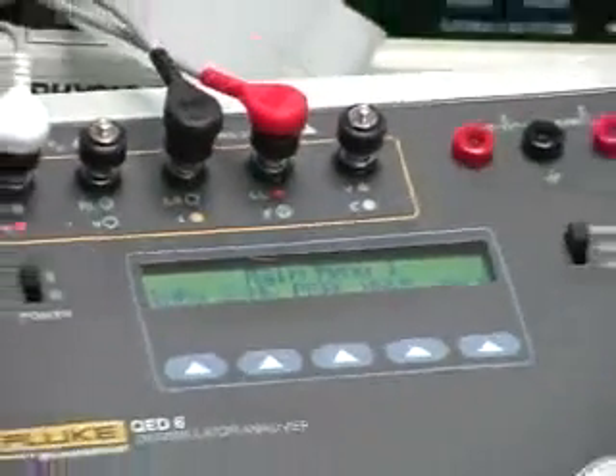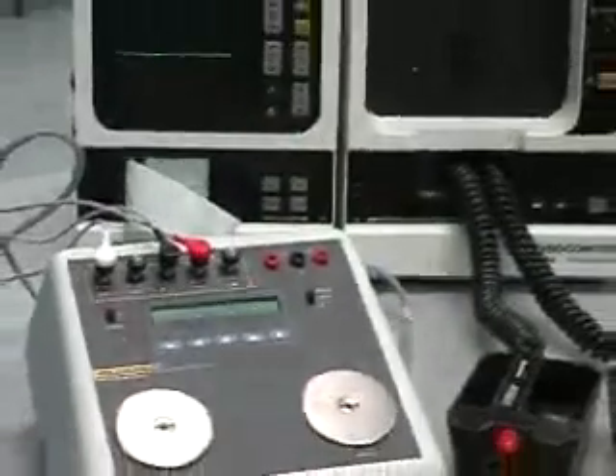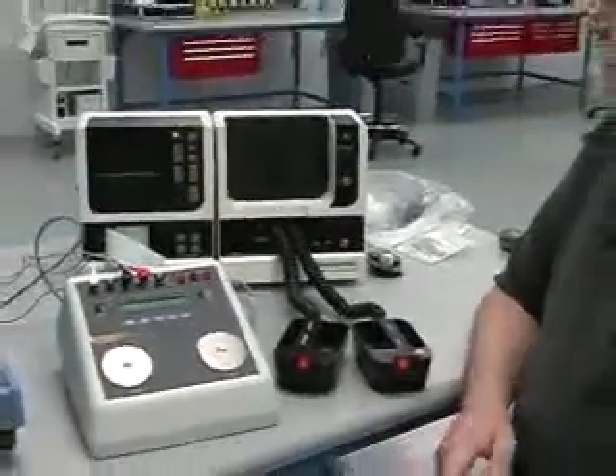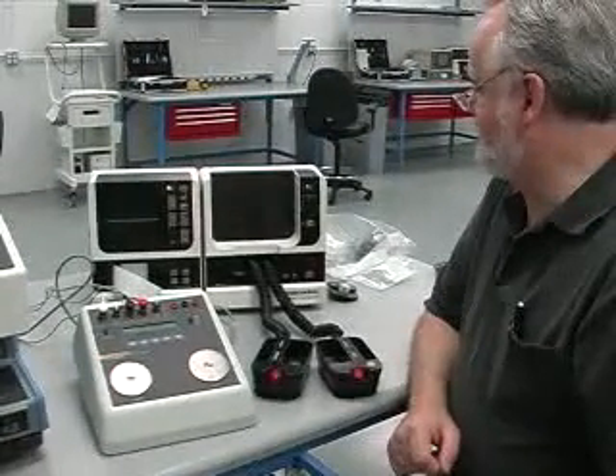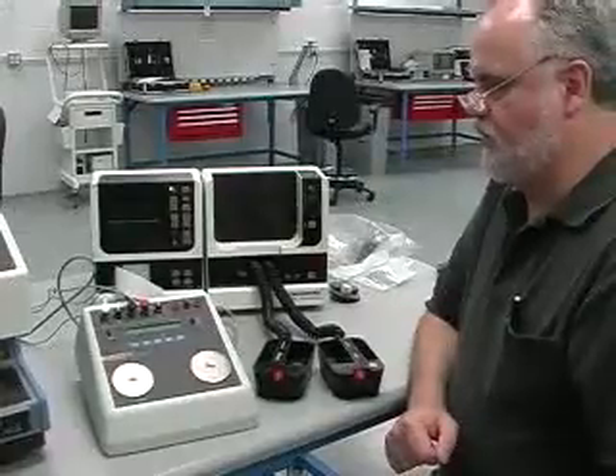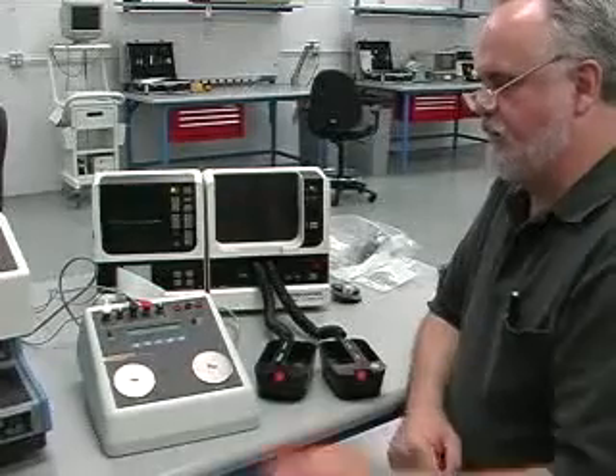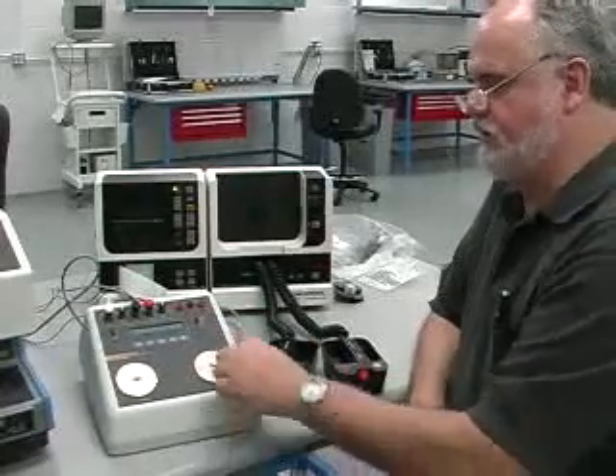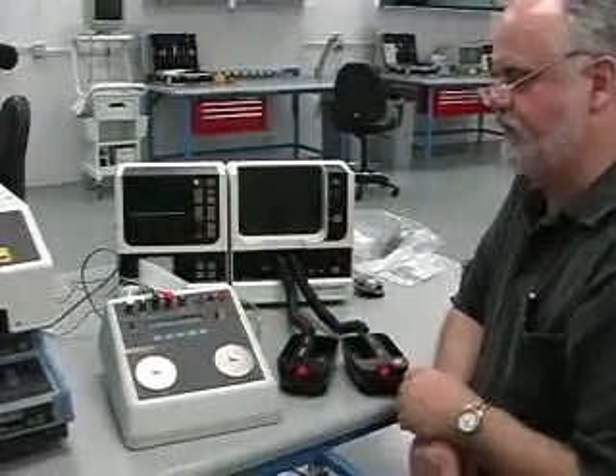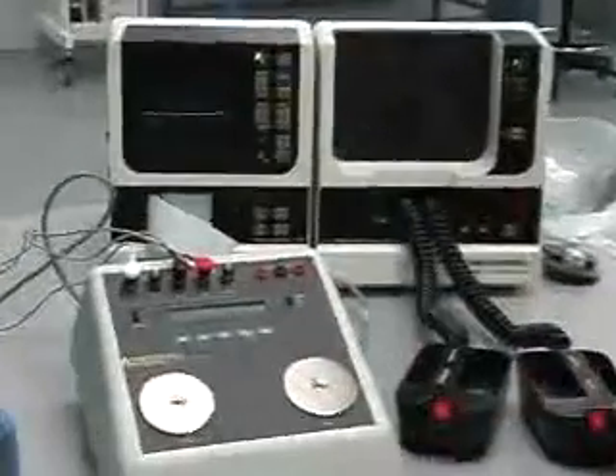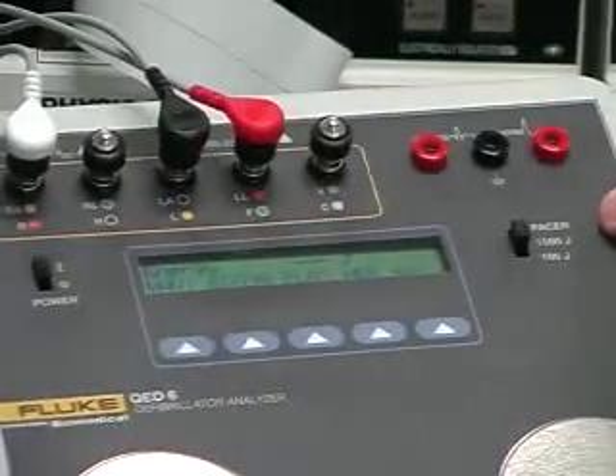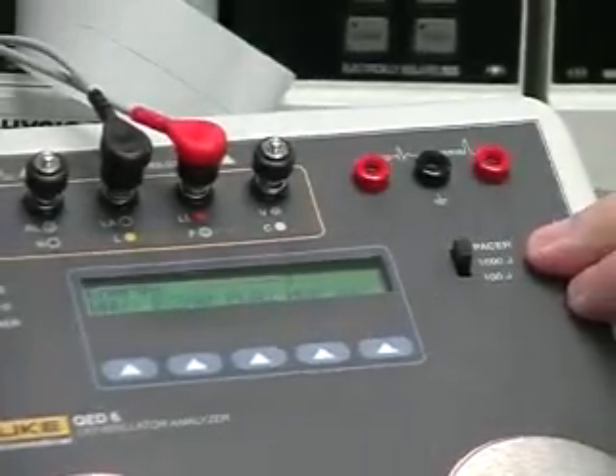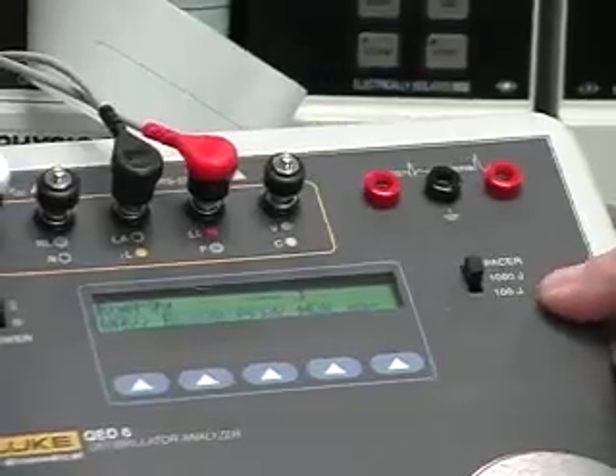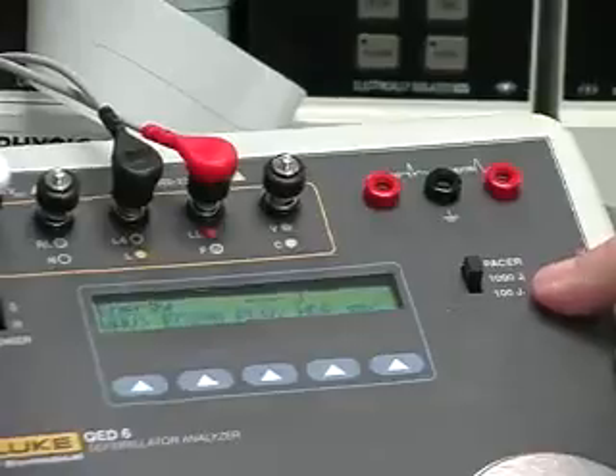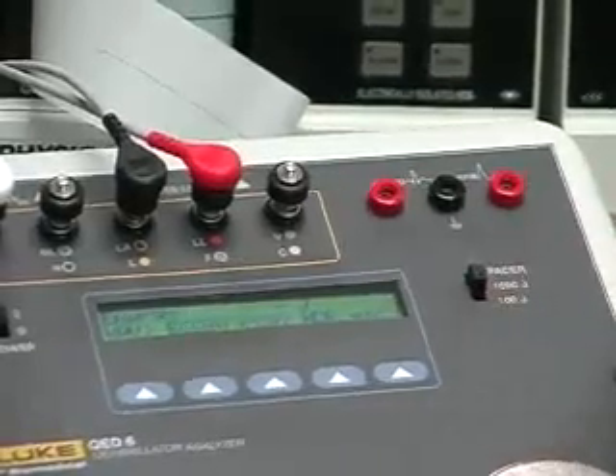Okay, we're going to be testing the Physio Control LifePak 8 defibrillator unit. This is a monophasic defib unit that does have energies up to 360 joules. To run those tests, you are able to measure it with the QED6. F1 is the energy push button on main menu 1, and with that, you have to make sure the range switch is in the right position. There are 2 switch positions for the defib, values over 100 or values under 100, or for the pacing capability.